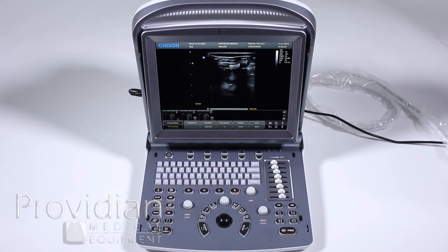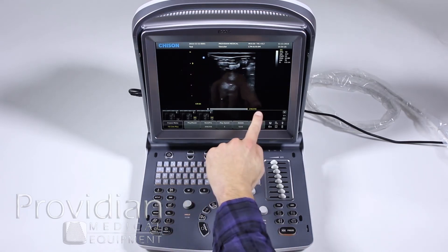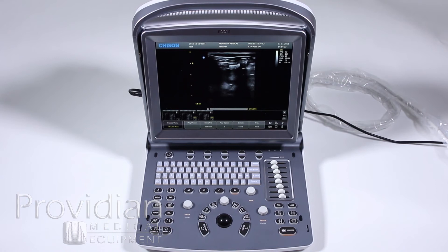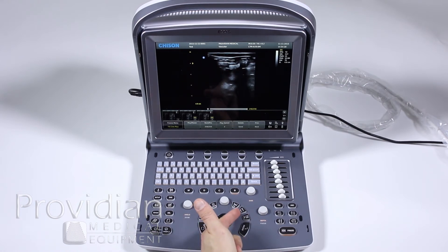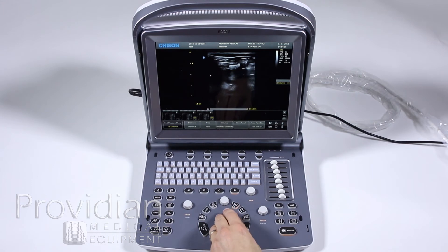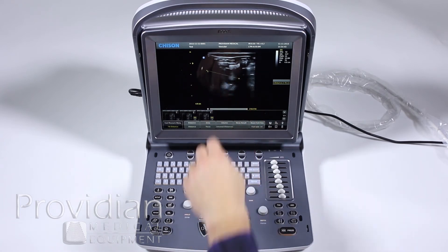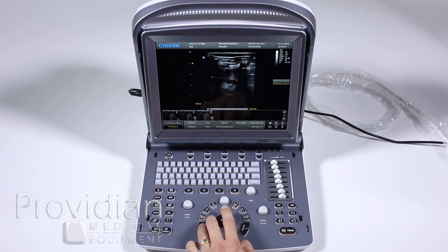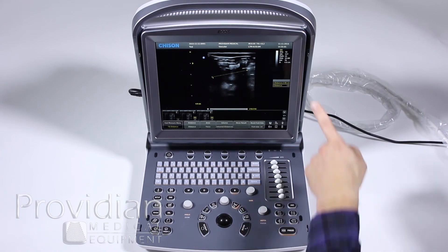To clear the arrows, hit the delete key. Now when you want to take a measurement, there are a few different ways. We'll start with the very basic measurement. First you need a frozen image — one way to tell is the frame number shown here and a little snowflake indicator, which means the image is frozen. To measure distance, push down and it gives you a cursor. Hit point one, then scroll to point two and hit enter. If you don't like where you placed point one, hit the update key to go back and forth to adjust that position. When you like where it is, hit enter and it shows you the results box.